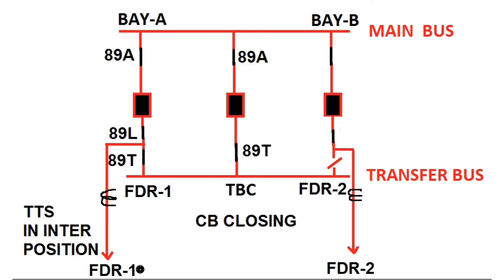In feeder 1 there exists a CRP panel, and in the CRP panel there exists a trip transfer switch. First we have to move this trip transfer switch to the inter position. After making this switch in inter position, we have to close 89A, 89T isolators of this feeder 1 bay. After this, the TBC breaker needs to be closed — unless the TTS switch of feeder 1 is made into inter position, we cannot close the TBC breaker.